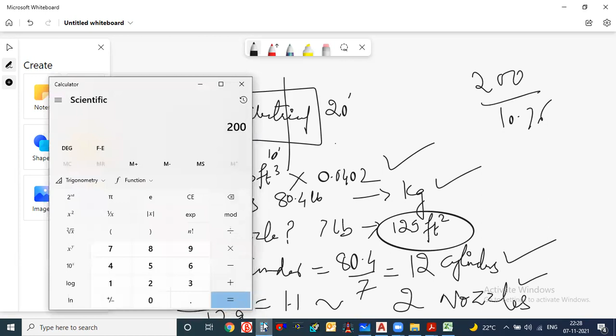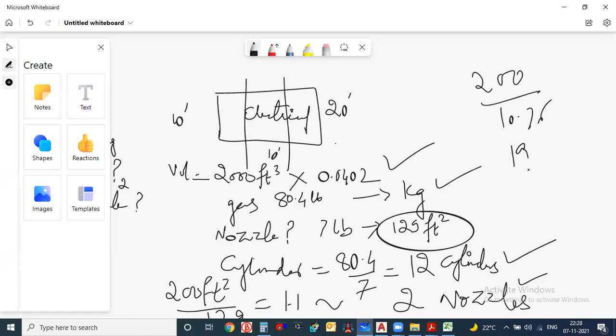Now here you see one calculator is also given, the FM200 gas fire extinguisher calculator. With this method also you can do it. Here, if I am giving the room area as 200 square feet, I will convert it into square meters by dividing by 10.76. So it becomes something around 19 square meters. I will write the area as 19 square meters, and room height is 3.5 meters.